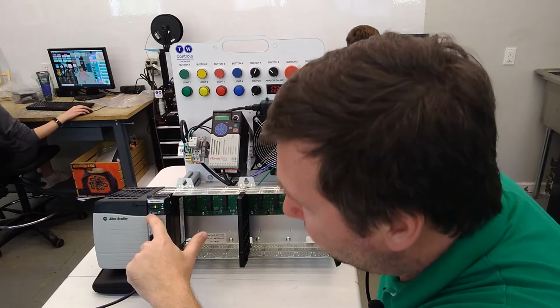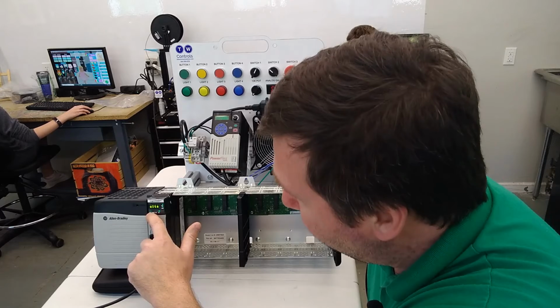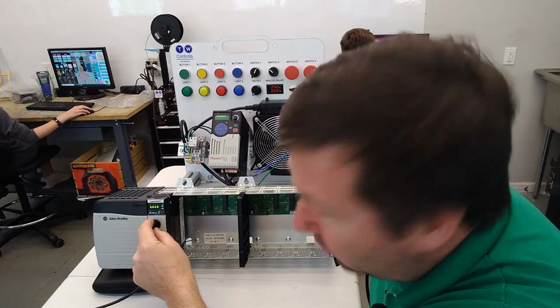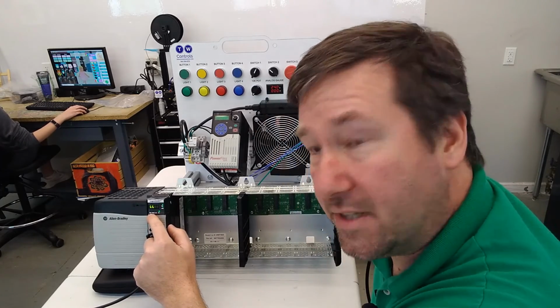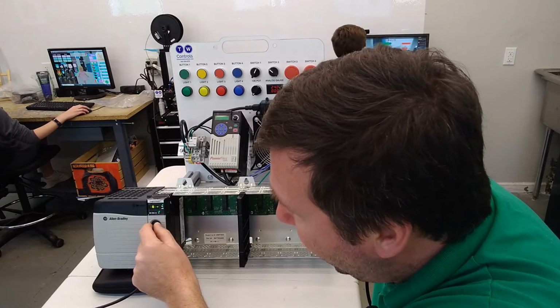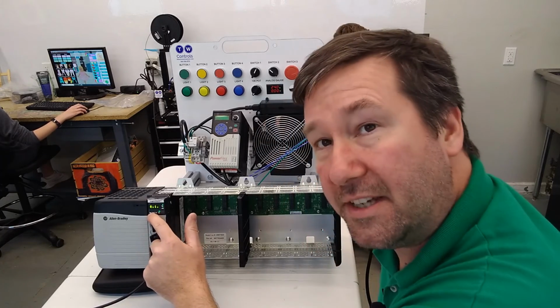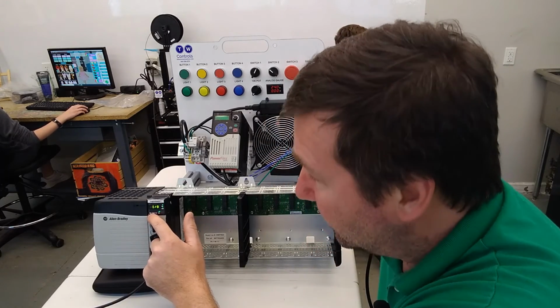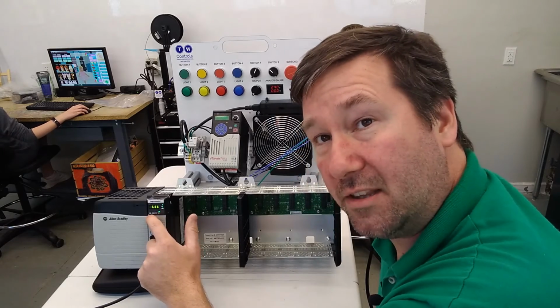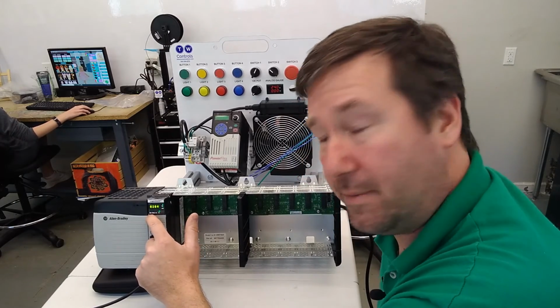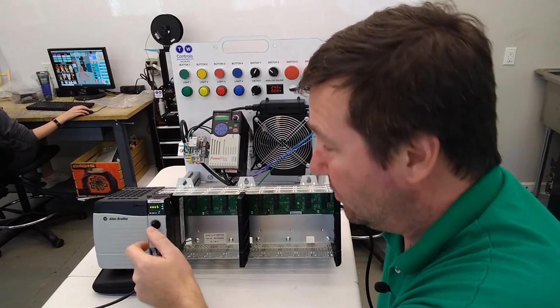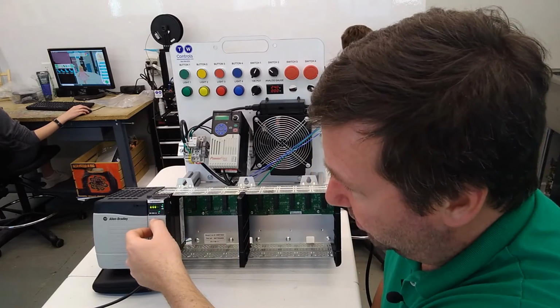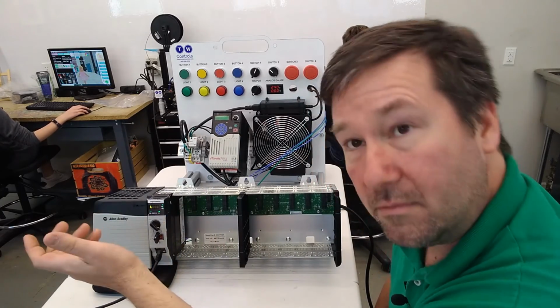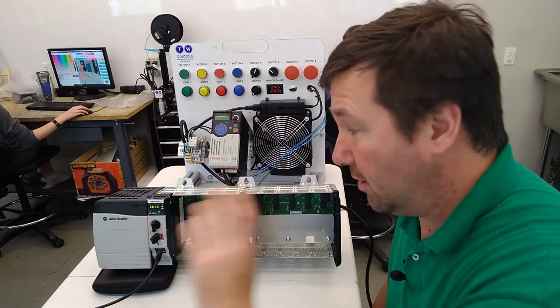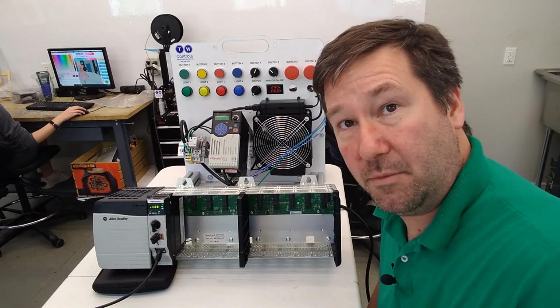And you have an indicator right here. It says run right here in green. When we switch it over to program, that run light goes out. If we switch it back to that middle position, that run light did not come back on because it is not running. So if you don't see that run light green solid on your PLC, it's not executing code in it. Now we'll switch it to run mode. It starts running. But really, there's no need to fiddle with a switch if your machine is broke.